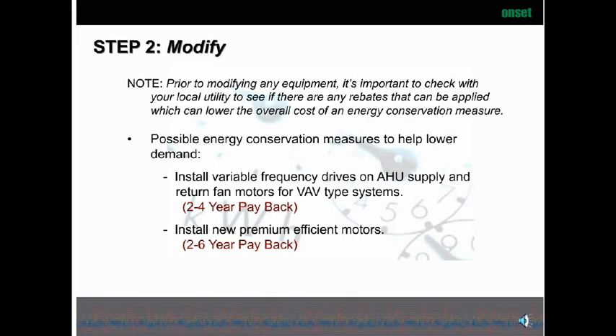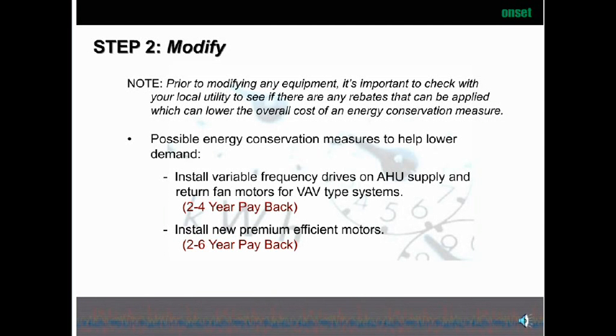After we've measured it, now it's time to modify. But prior to modifying, you should check with your utility — if you've identified pieces of equipment that need to be fixed, there may be utility rebates available to lower your overall cost. These rebates are available in the Northeast and California, and pretty much across the country. One possible energy conservation measure is installing variable frequency drives on air handling systems — supply and return fans and motors. These are typically used in VAV type systems, though you can apply them in constant volume systems as well with care.